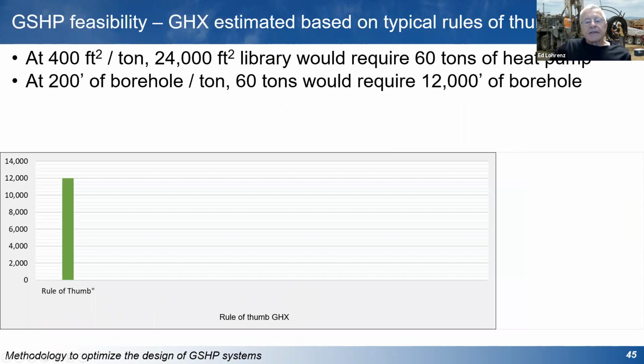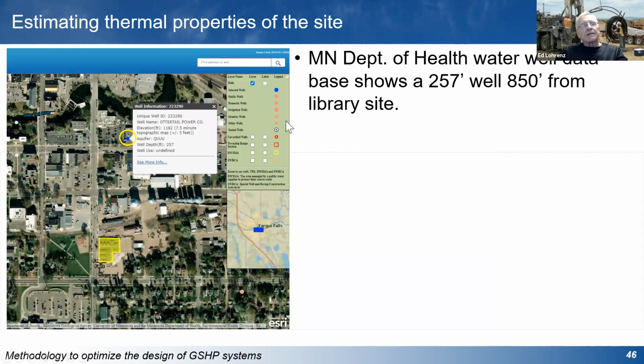So what does that do to the size of the boreholes that are needed? If we take a look at what the rules of thumb would suggest, 12,000 feet of borehole, based on 400 square feet per ton and 200 feet of drilling per ton, is what would be suggested. And if that was told to the client, the cost of drilling 12,000 feet might be more than their budget could withstand. So looking at how to start with the system, where do we go from here?